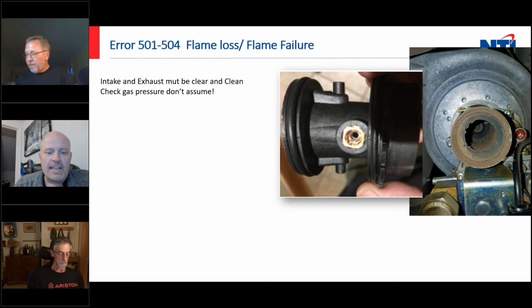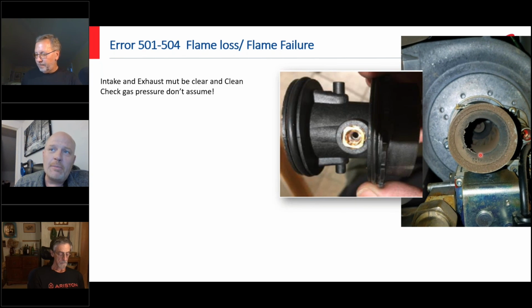So we've got test ports. Look for this kind of stuff. I mean, if you see this, there's obviously a problem. One that's a little less obvious though, pull out these Venturi inserts, and if you look, there's just a tiny bit of white corrosion in there. That's enough to actually choke the gas flow in the boiler to where it won't stay running anymore. So anything that's got a flapper Venturi, pull it out, inspect the orifices.